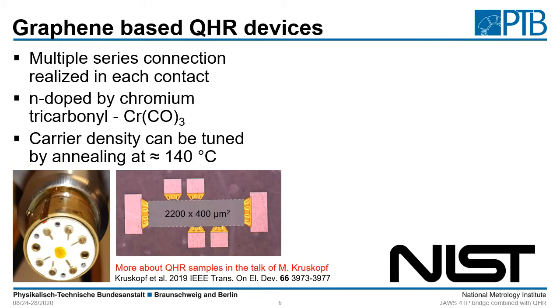The first graphene based quantum hall device I want to show you is kindly provided by NIST. The design is made in a multiple series connection in each contact. So it is not only an external triple series connection but all these contacts are made of different branches to have the multiple series connection already realized on the chip. The devices are doped by chromium tricarbonyl, and this method allows us to change the carrier density even after manufacturing. This is done by annealing at a temperature of about 140 degrees Celsius, and if you want to change the carrier density in the other direction you have to expose them to air and wait a while, then reheat them to the desired carrier density.